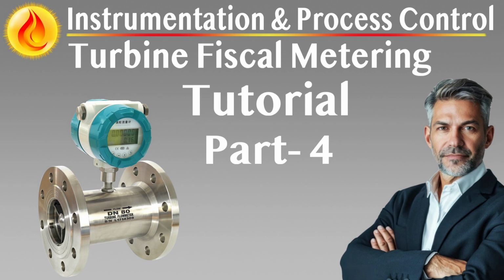Detector systems used to define the start and stop of the prover volume must be repeatable to a resolution compatible with this pulse density. The sphere velocity must not exceed 3 meters per second to prevent hydraulic shock and ensure uniform travel. At each end of the calibrated section, dual redundant detector switches must be installed to prevent proving interruption in the event of a single detector fault.